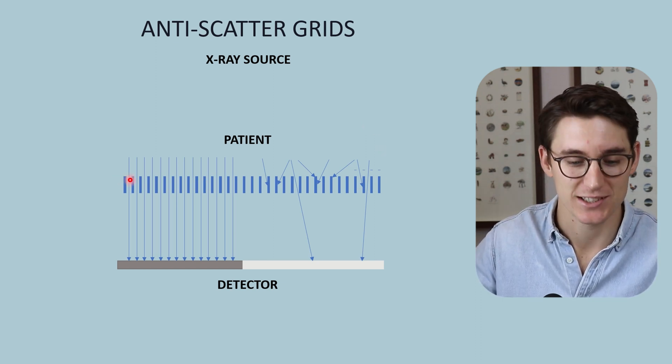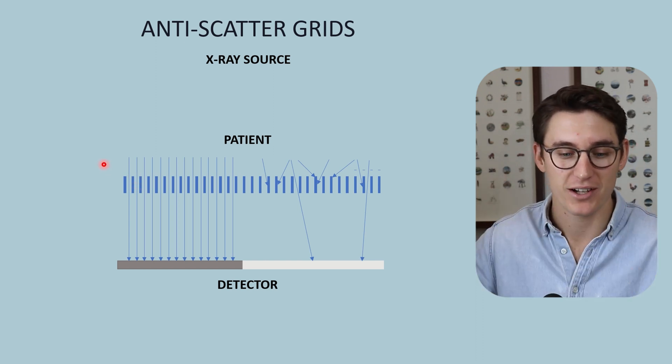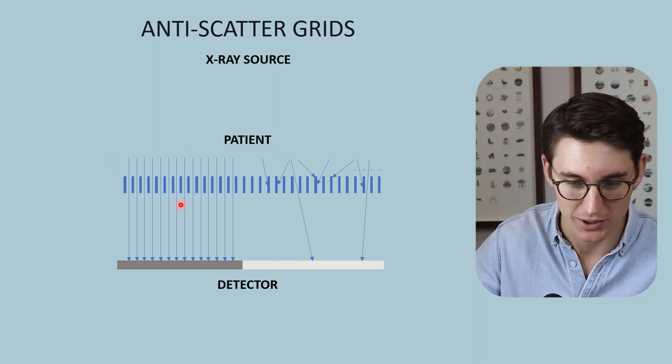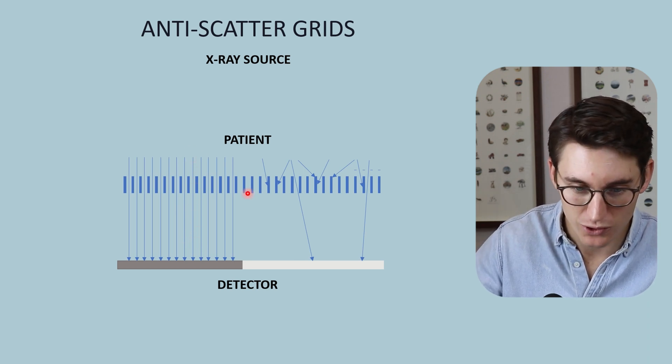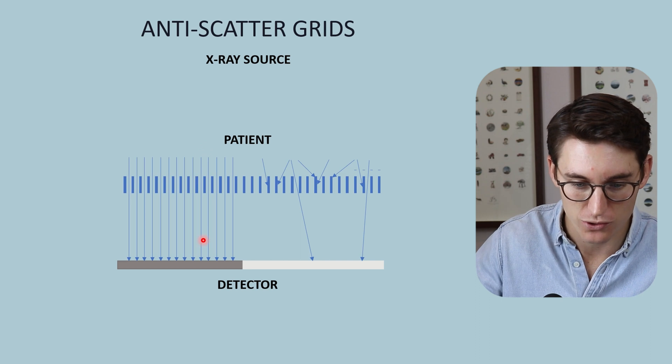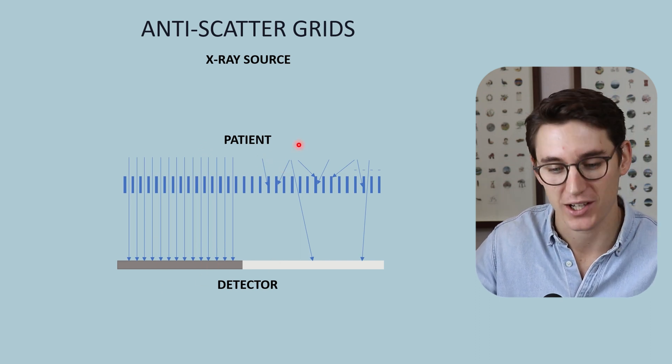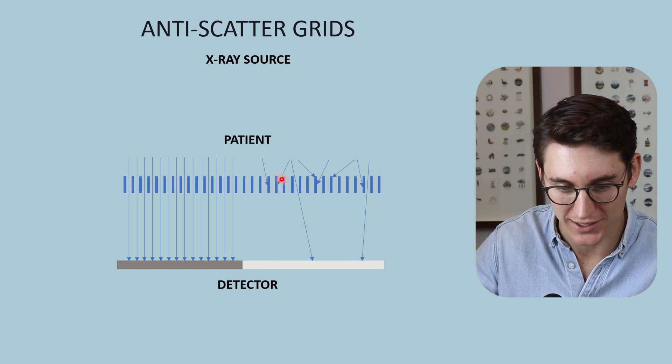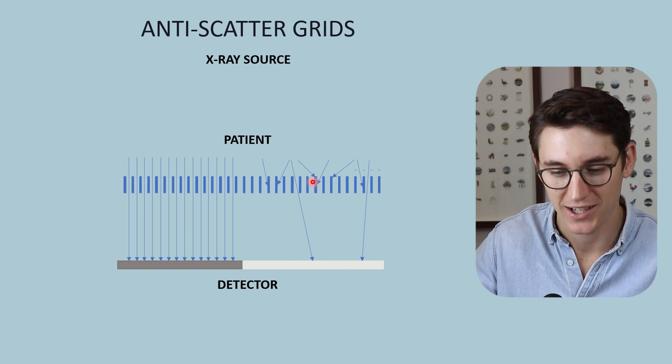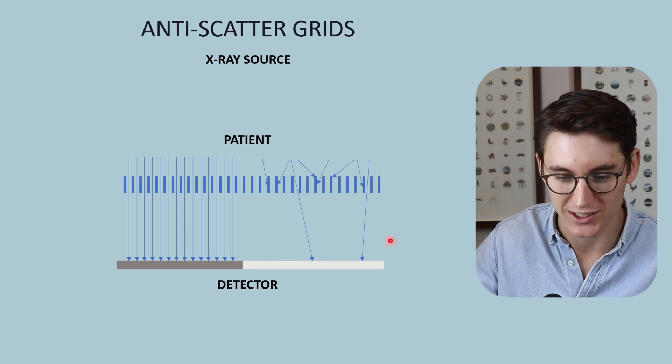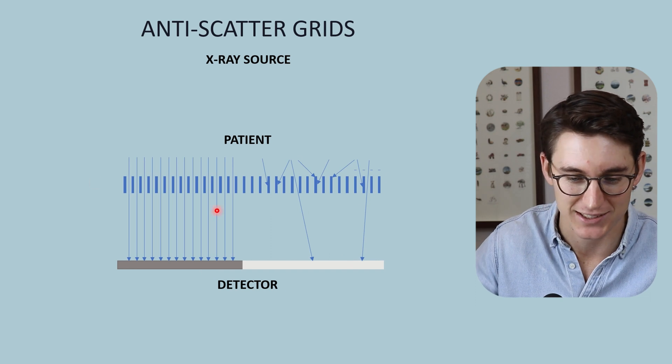Now what our anti-scatter grid is, it's a series of highly attenuating septa that are parallel to our primary x-ray beam. Transmitted x-rays that are parallel to these anti-scatter grids will pass through the grid and hit our detector. Scattered x-rays that come off at an angle will be attenuated by these grid septa, and very few of them will reach our detector. This is a way of reducing scatter contribution to the exposure to our detector, and it's known as an anti-scatter grid.